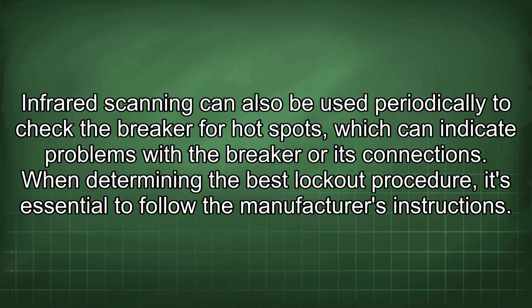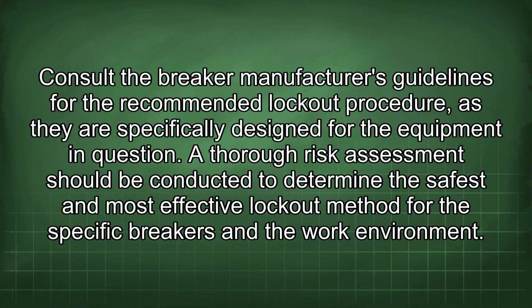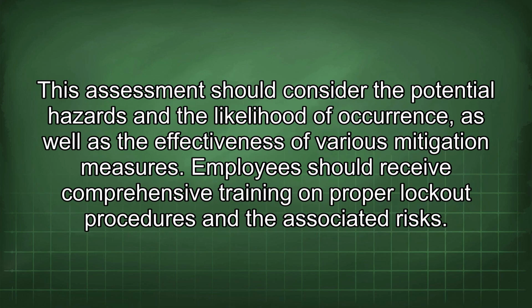Infrared scanning can also be used periodically to check the breaker for hot spots, which can indicate problems with the breaker or its connections. When determining the best lockout procedure, it's essential to follow the manufacturer's instructions. Consult the breaker manufacturer's guidelines for the recommended lockout procedure, as they are specifically designed for the equipment in question. A thorough risk assessment should be conducted to determine the safest and most effective lockout method for the specific breakers and the work environment. This assessment should consider the potential hazard and the likelihood of occurrence, as well as the effectiveness of various mitigation measures.